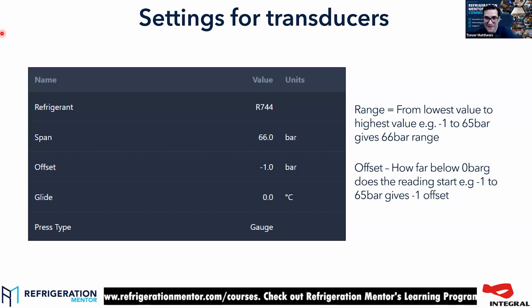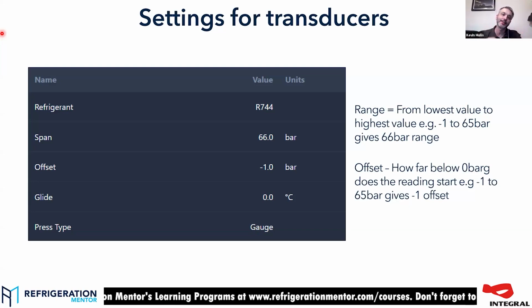And there's no reason you can't use, and they do, a -1 to 99 as well. What we would see, just a slight divergence, when we were doing some Tesco work a few years ago, another major retailer in the UK, when there was no -1 to 59s available, you could use a -1 to 99 on the case. But if you used a programming stick, like we showed previously when we did Danfoss, to dump the program into all the cases, you've got to allow for the fact you've changed the transducer, otherwise you'll get some craziness on the readings.